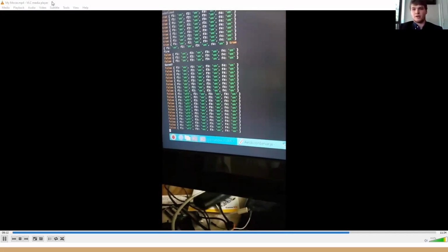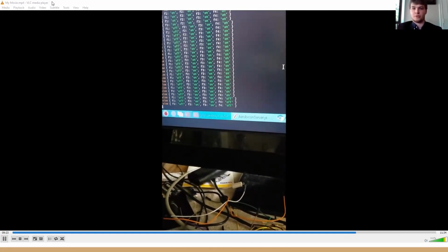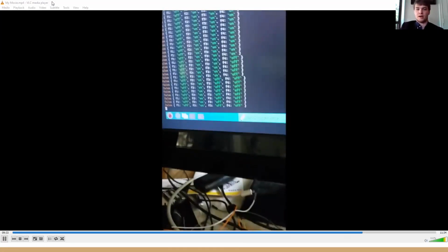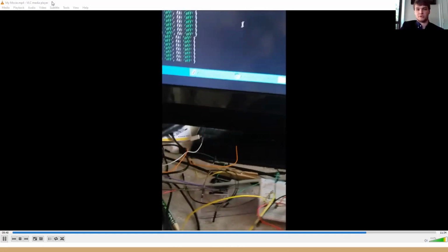So there should be 2 criteria to turn it off. One, if the user set, this is another thing I personally want to implement. We want to have a user time window so that the user can say, yeah, we want our pump to run for 30 minutes or something to that degree. So it'll check if within that 30-minute time frame it hasn't reached F2, turn off the pump. If it has reached F2, still turn off the pump. But what that will allow is if it's above F3 and it pumps down and doesn't reach F2, it'll still turn off.